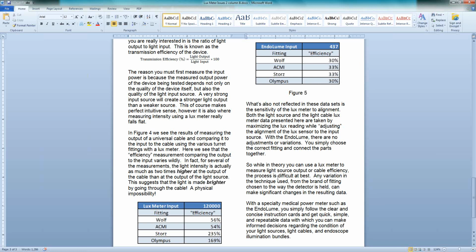So that's the difference between trying to use a lux meter and an EndoLume. With a lux meter, you have to be very careful, the alignment is very sensitive and critical. If you change the type of fitting or the turret setting, you completely change the results you get. With the EndoLume, a cable is a cable. It doesn't matter which manufacturer or which settings you use, they should all be about the same performance.